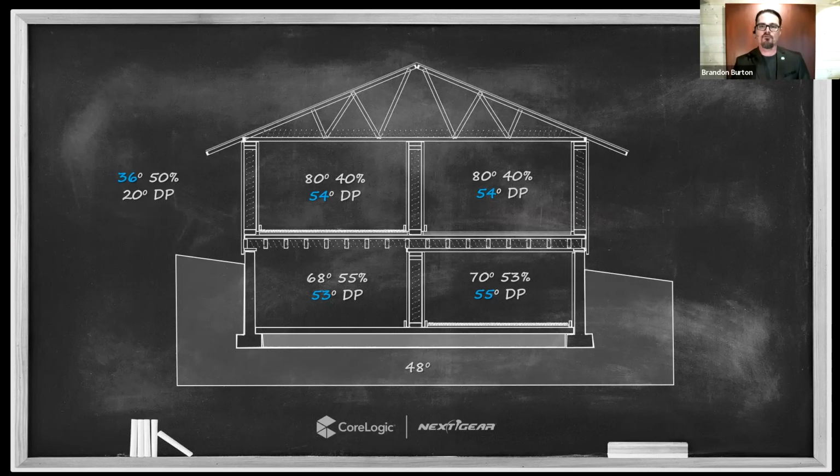And we identified this problem right up front. And these challenge areas began drying at the same time the rest of the building does. And instead of 5, 6, 7, 8 days where most of that time is focused on these problem areas towards the back end of the project, they were drying in concert or in synergy with everything else. So again, this helps me identify that challenge, because at 36 degrees outside with a 54-degree indoor dew point, those exterior surfaces or those materials in contact or influenced by outdoor air temperature, they're not going to dry.